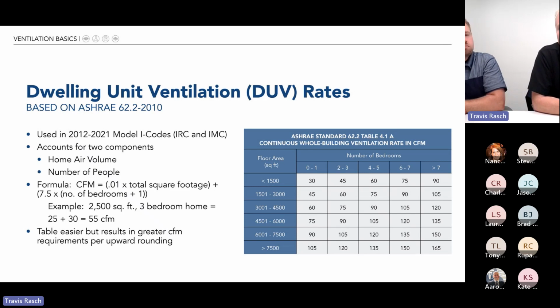So I mentioned earlier the most common form to calculate dwelling unit ventilation rates is the 2022 version of 62.2. So again, ASHRAE is an engineering society. They do a lot of research. Back in the day, they determined that the fresh air we need in a home is based on two factors. One is the total air volume in a home. Obviously, the more cubic feet of air you have in a home, the more stale air you need to get out, and fresh air to get in. And then the number of people. They looked at it that each person should have so much CFM.